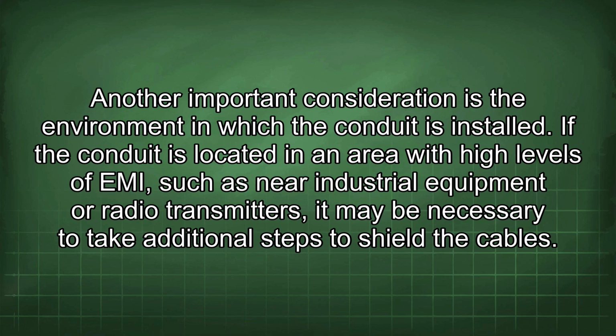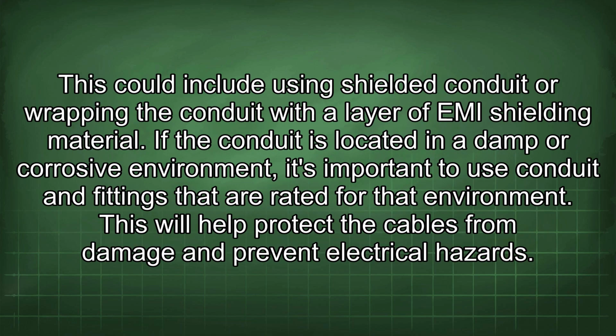If the conduit is located in an area with high levels of EMI, such as near industrial equipment or radio transmitters, it may be necessary to take additional steps to shield the cables. This could include using shielded conduit or wrapping the conduit with a layer of EMI shielding material. If the conduit is located in a damp or corrosive environment, it's important to use conduit and fittings that are rated for that environment. This will help protect the cables from damage and prevent electrical hazards.